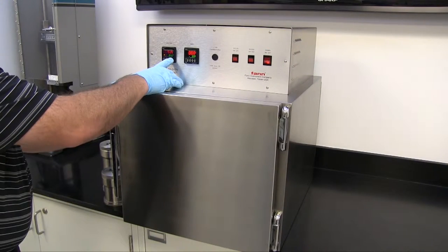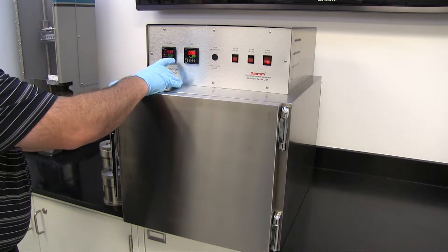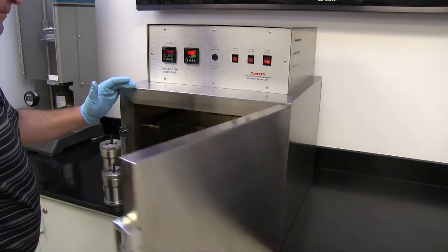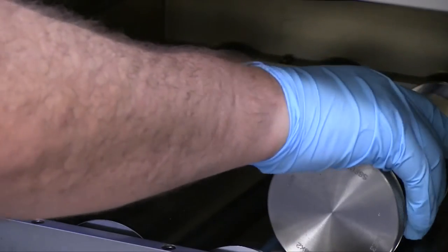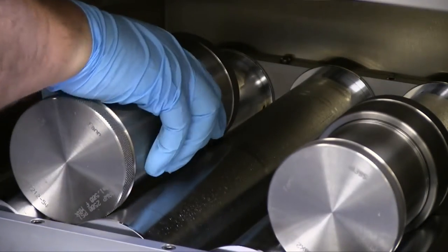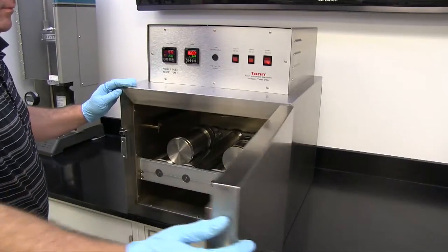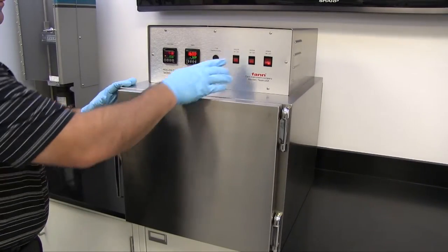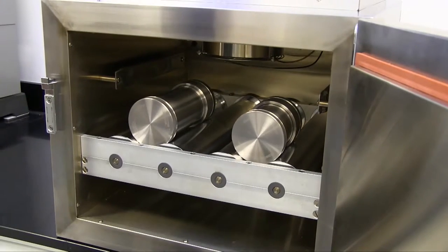The roller ovens are primarily designed for laboratory use. These roller ovens provide an excellent method of aging fluid samples. High-temperature aging cells containing sample fluids are placed in the roller oven. There they are subjected to moderate heat and agitation, or rolling, on power-driven rollers. Samples may also be heated without rolling, called static aging. They can also be used for drying samples and mixing fluid chemicals.